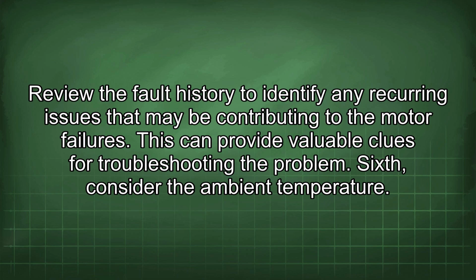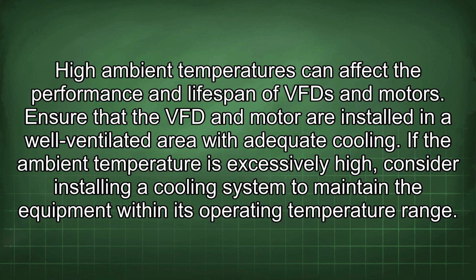Sixth, consider the ambient temperature. High ambient temperatures can affect the performance and lifespan of VFD and motors. Ensure that the VFD and motor are installed in a well-ventilated area with adequate cooling. If the ambient temperature is excessively high, consider installing a cooling system to maintain the equipment within its operating temperature range.